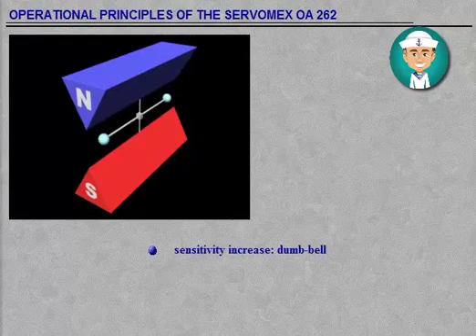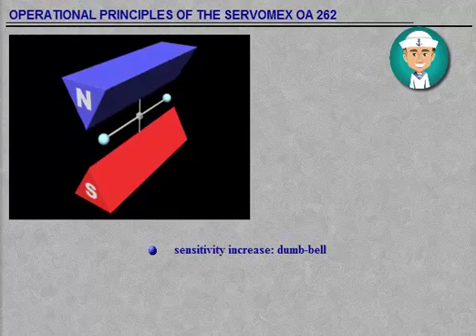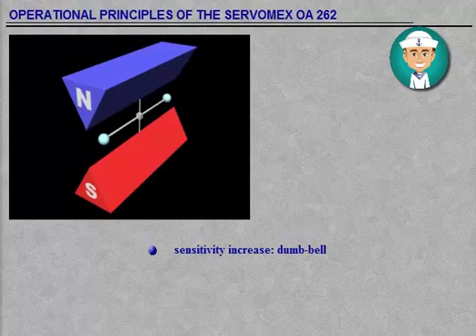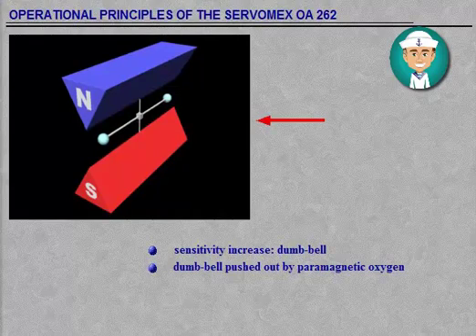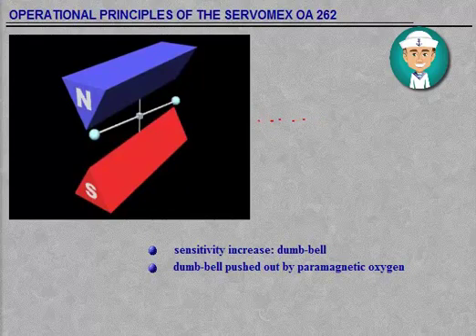In practice, in oxygen analysers, the convenience and sensitivity of Faraday's arrangement is increased by having a sphere at both ends of the bar. This forms a dumbbell, which is sealed from the gas surrounding it. The dumbbell is suspended in a symmetrical non-uniform magnetic field, and being slightly diamagnetic, it takes up a position away from the most intense part of the field. When the surrounding gas contains oxygen, the dumbbell spheres are pushed further out of the field by the relatively strongly paramagnetic oxygen.